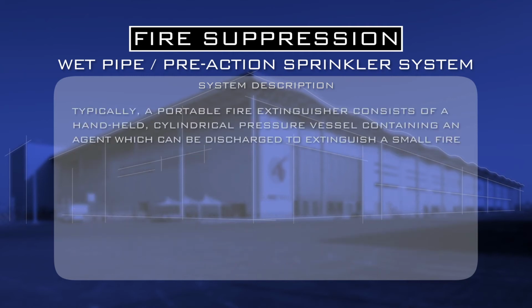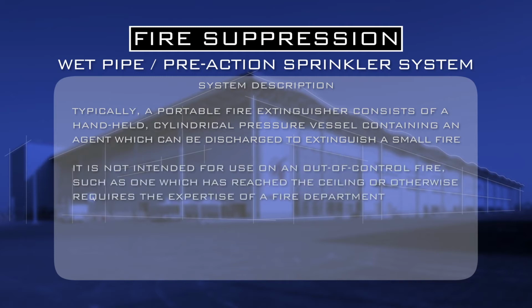Typically, a portable fire extinguisher consists of a handheld cylindrical pressure vessel containing an agent which can be discharged to suppress a small fire. It is not intended for use in an out-of-control fire, such as one which has reached the ceiling or requires the expertise of the fire department.